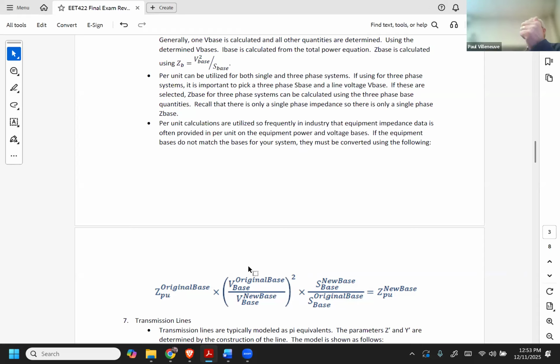Remember, we looked at two different data points: transformer tests and a generator test sheet, and in both instances the data was given in per unit, not actual ohms. The only time you'll actually see ohms for impedance data is for a transmission line, because you don't purchase a transmission line from a local distributor, you construct it. So it's designed and constructed, and the impedances are determined based on the topography and your design. So you have to calculate it, and at that point you're calculating an actual impedance.